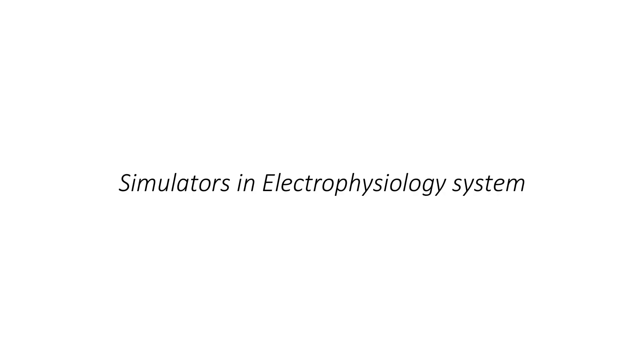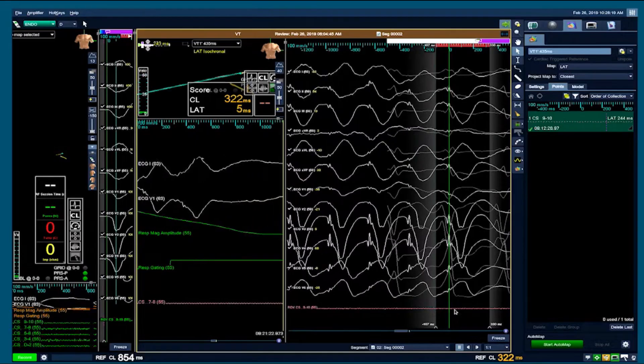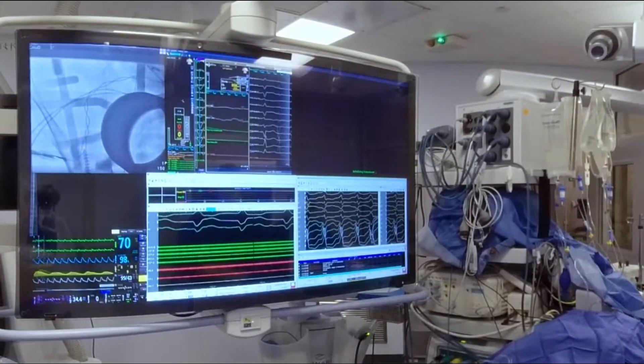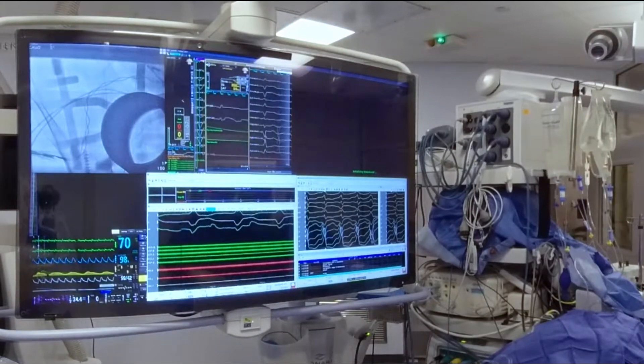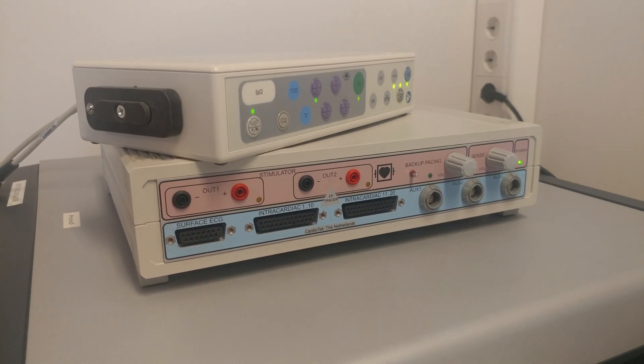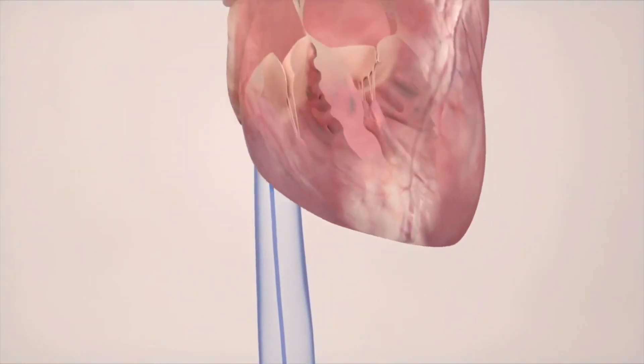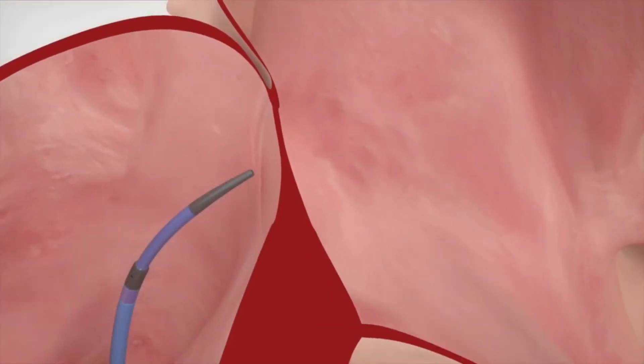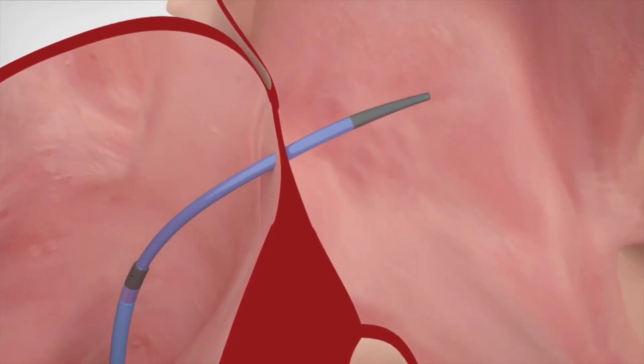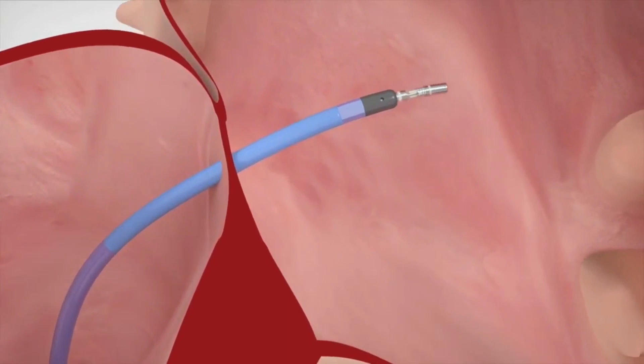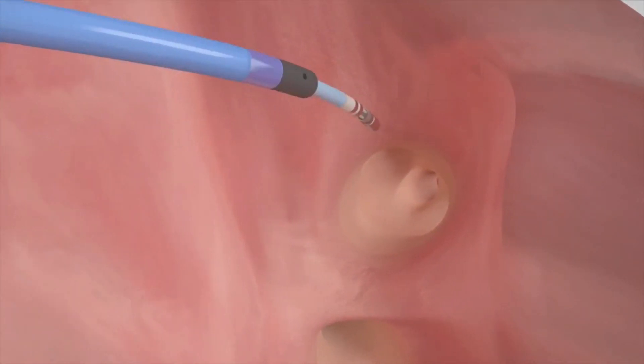The stimulator delivers a constant current output through one or more output channels in order to pace the heart and deliver at least four coupled extra stimuli. The stimulator can be connected directly to the junction box where pacing poles are used to connect electrode pairs for pacing. Or, as is more commonly done today, the stimulator output is connected to the recording system where the computer controls which electrode pairs are used for pacing. This allows for different stimulation protocols to be set up using a multitude of specific electrode sites for stimulation.